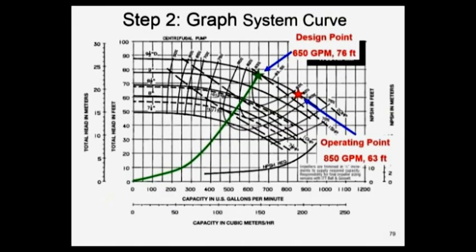Now what do we do? We very simply take those and we plot them onto your pump curve. I'm going to plot them right now in red. There you go. So the red line with the red stars is the real system curve. The one that's really happening and giving you 850 at 63. The green line was what you thought was the theoretical system curve. It was going to give you 650 at 76. But the bottom line is we don't need 76 feet of head, do we?